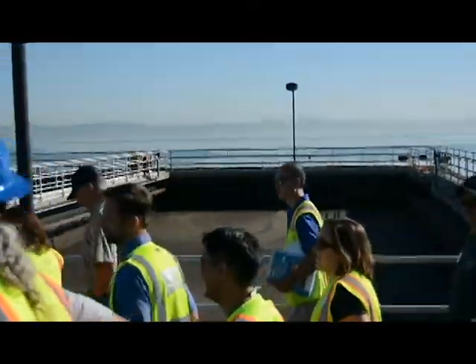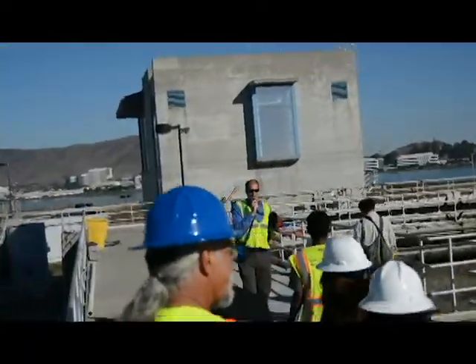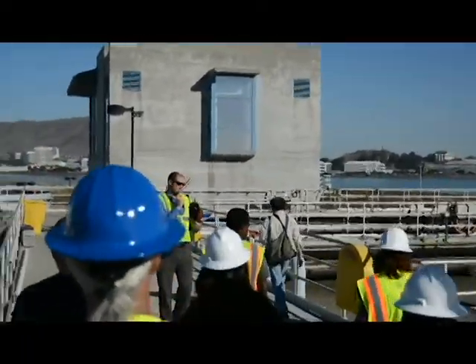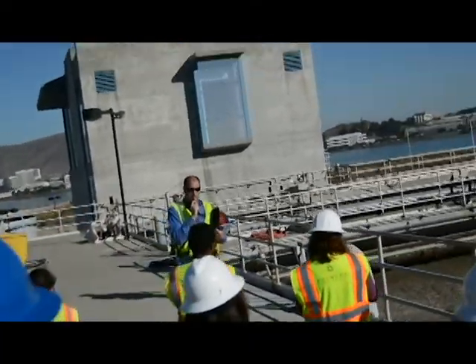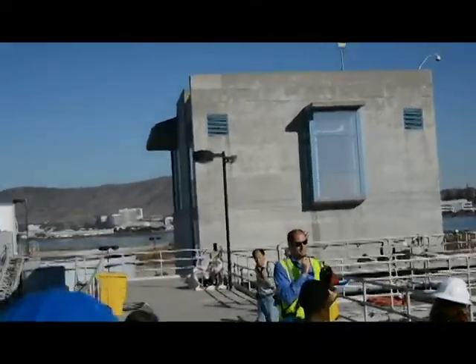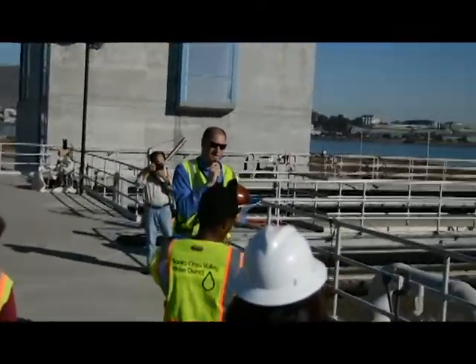The next tank is under aeration right now, so you see the bubbling going on. And again, the concept here is fill that tank, typically under anaerobic conditions. So we're trying to select the proper bacteria and avoid the filamentous, but you see the nice foam on top. We have plenty of nocardia growing here.